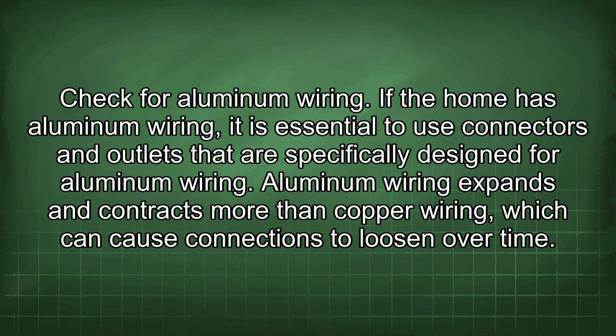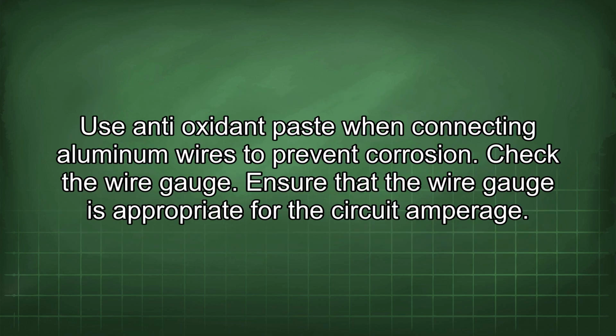Check for aluminum wiring. If the home has aluminum wiring, it is essential to use connectors and outlets that are specifically designed for aluminum wiring. Aluminum wiring expands and contracts more than copper wiring, which can cause connections to loosen over time. Use antioxidant paste when connecting aluminum wires to prevent corrosion.